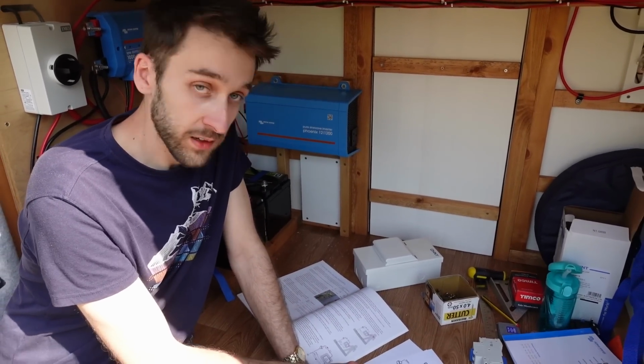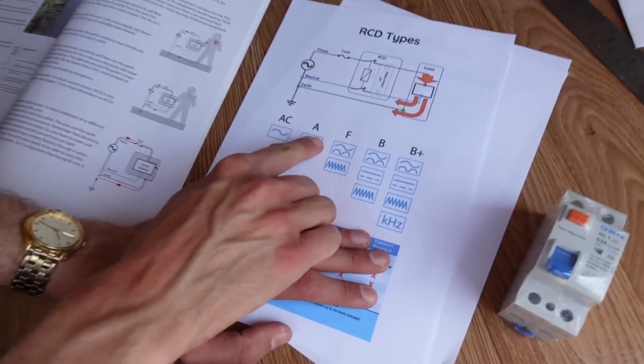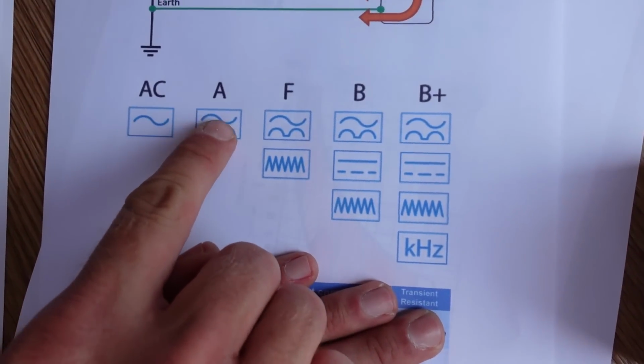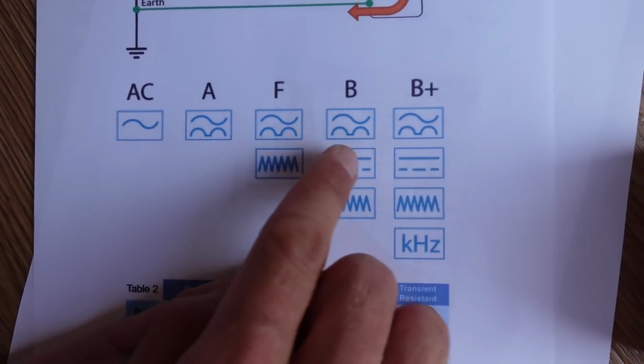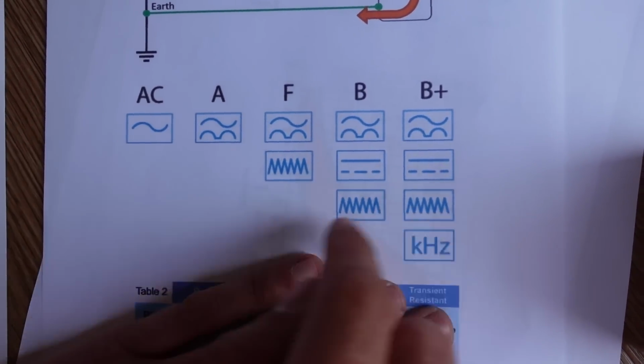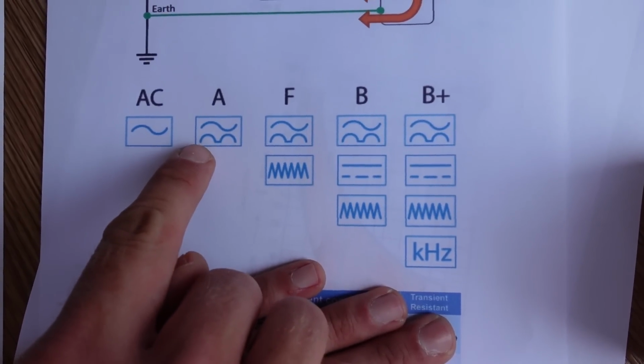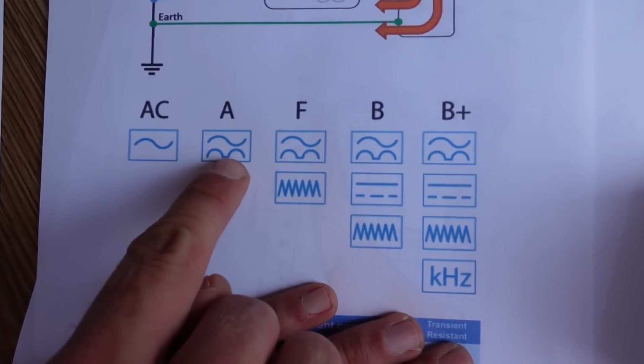For the RCD to be properly effective, it should detect a little bit of DC as well, and that's where type A comes in. As you go up the rankings you get everything from the previous type plus something else, so type A also detects a little bit of pulse DC.